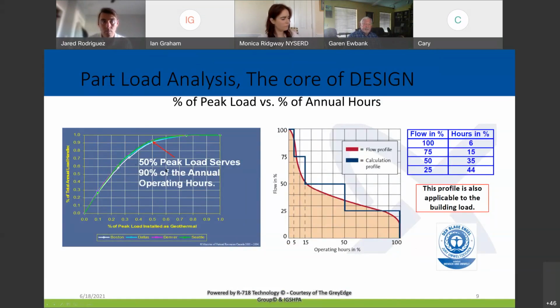On the left, we'll see that 50% of the peak load serves 90% of the annual operating hours. Now, in Europe, they have a similar rule called the Blauer Engel rule, on a pumping system for water distribution inside a building for district systems. We can see very similarly that 50% is about, in their case, 79%.